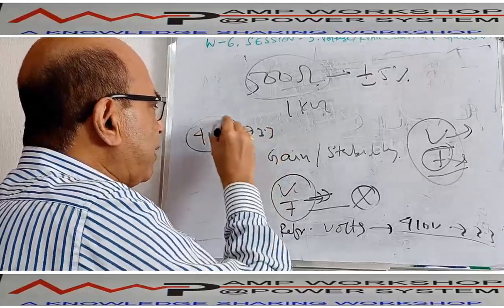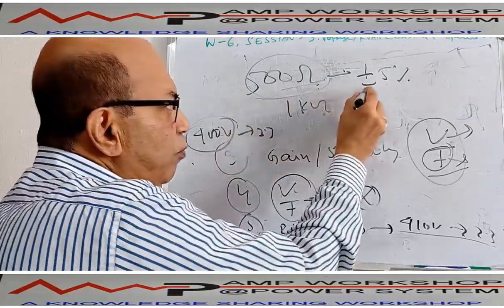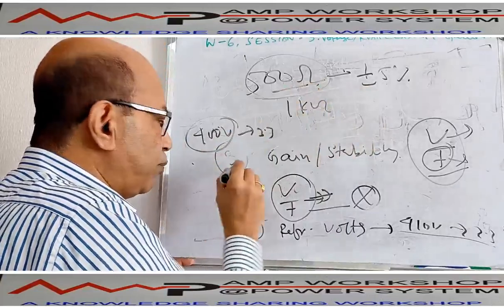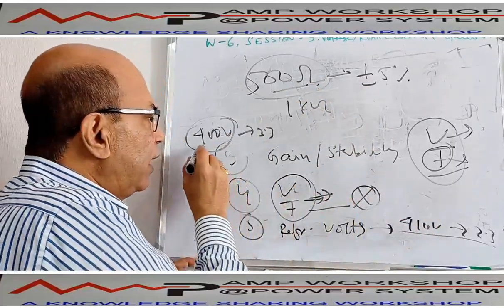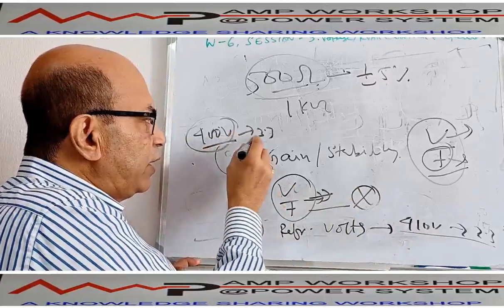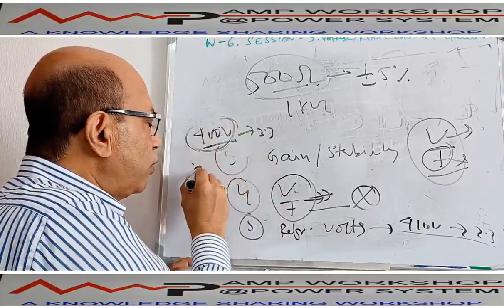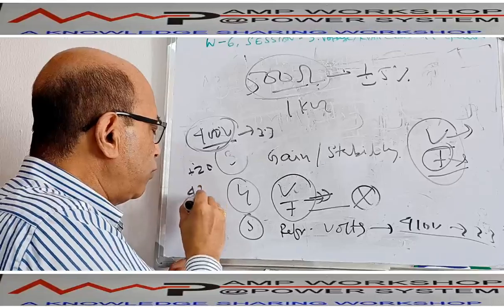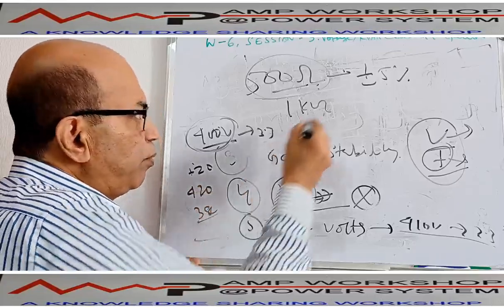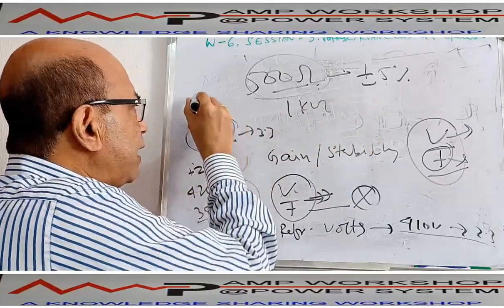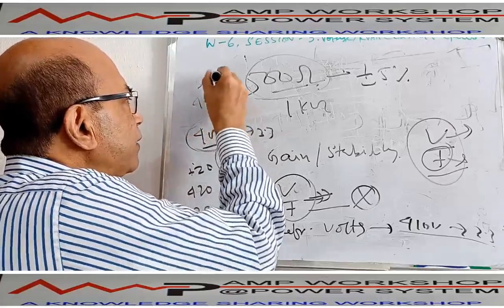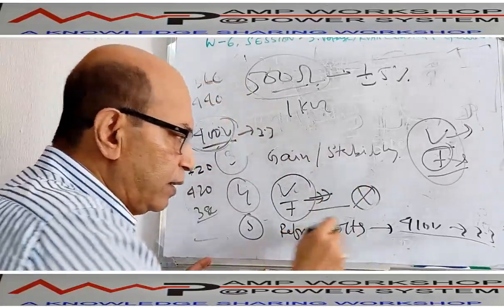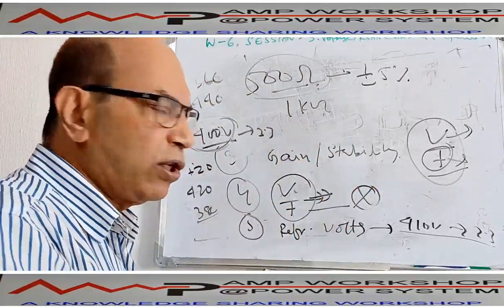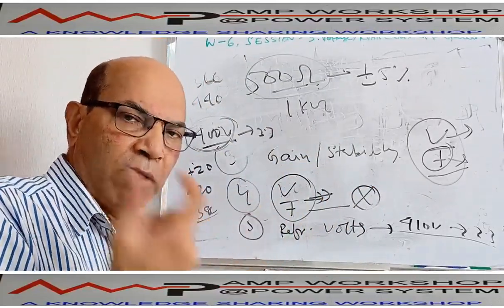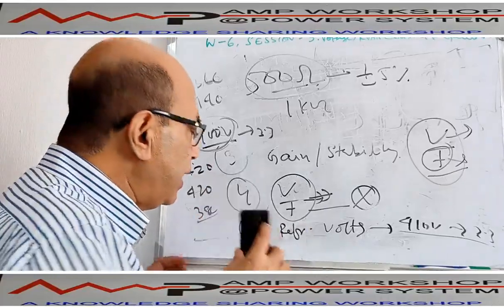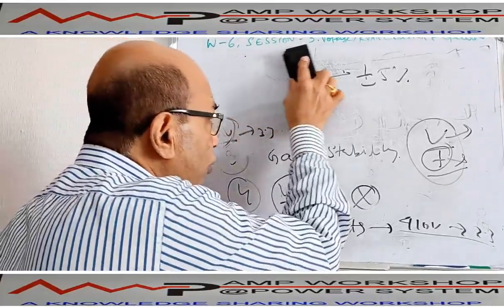So we can change 5% of this. If you put a 500 ohm resistance with this circuit, what will happen? It will change 5% of this voltage, meaning 20 volt plus, so it goes from 420 to 380. But if you put 1K, it will go 10%. That means it can go to 440, or it can come down to 360 volt. That variation is also there. This is another switch. These are the rotating switches which you can adjust during commissioning time, and you can change the setting accordingly. In addition to this, there is another lot of DIP switches.